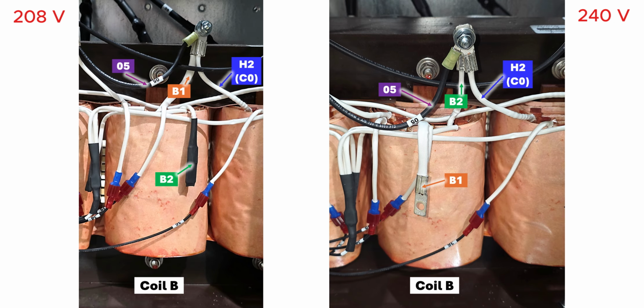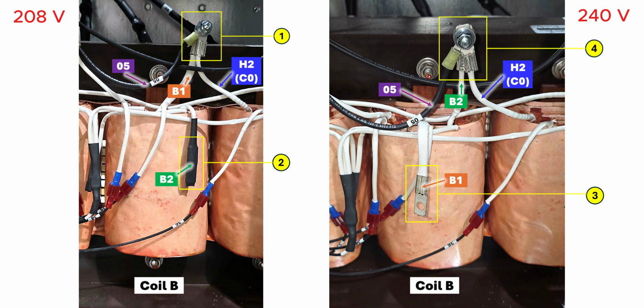Continuing the process now with coil B, we'll swap the wires that connect to H2. Number 1, remove the shrink wrap covering the H2 tap connections. Number 2, remove the shrink wrap covering wire B2. Number 3, keeping H2 connected to wire 05 from the AC circuit breaker, pull wire B1 out. Number 4, place wire B2 together with wires H2 and 05. Tighten the lugs for these wires together. Later, we'll shrink wrap the wires connected at H2 and separately wrap the unused wire B1.